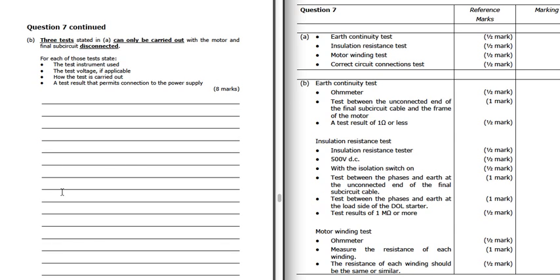The second part asks you to describe the tests that can be carried out with the motor disconnected. So for each of these tests, we want the test instruments, the test voltage, how the test is carried out, a test result that permits connection to the power supply. So we need the answer or the result that's going to say that it's okay. So you need to know these tests. These earth continuity and insulation come up all the time. We've got the addition of the motor winding test. That's just measuring the resistance of each winding and making sure they're very similar.